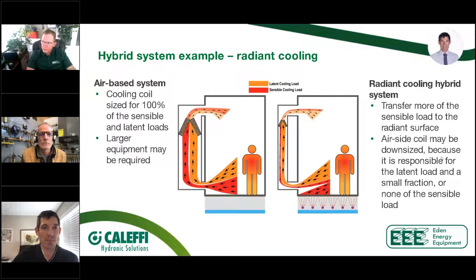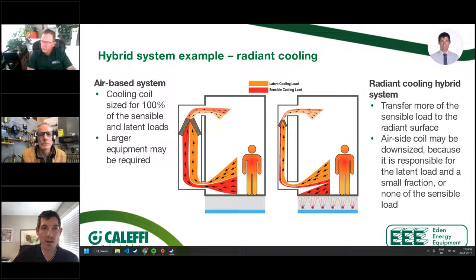So this is, I think, the best case scenario of a hybrid system example, a radiant cooling system. And again, this is for commercial new construction. Adding radiant cooling to an old leaky house in Missouri is probably a bad idea for a variety of reasons. You don't have the envelope, you don't have the control system, you're not really set up for success. But with new construction, commercial, the building codes and the ASHRAE standards that would apply already check the boxes of some of the prerequisites you would need to do radiant cooling. So it sets you up in a good way.